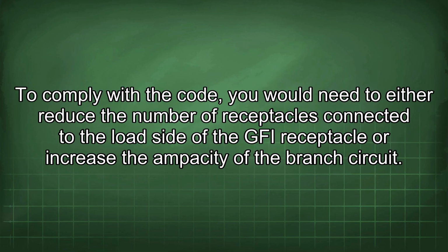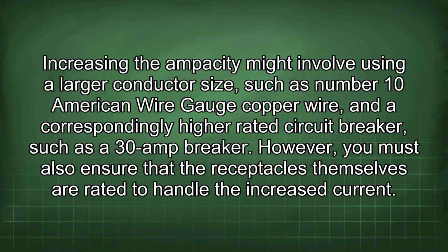To comply with the code, you would need to either reduce the number of receptacles connected to the load side of the GFI receptacle or increase the ampacity of the branch circuit. Increasing the ampacity might involve using a larger conductor size, such as number 10 American wire gauge copper wire, and a correspondingly higher rated circuit breaker, such as a 30 amp breaker. However, you must also ensure that the receptacles themselves are rated to handle the increased current.